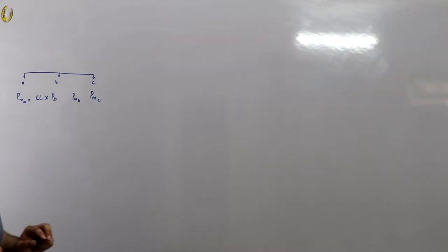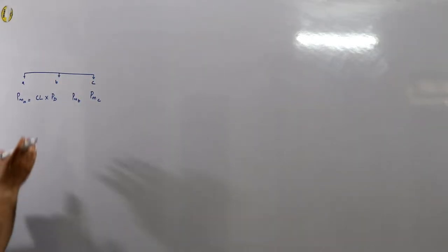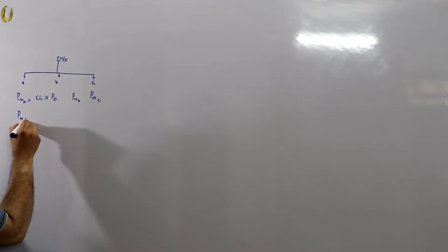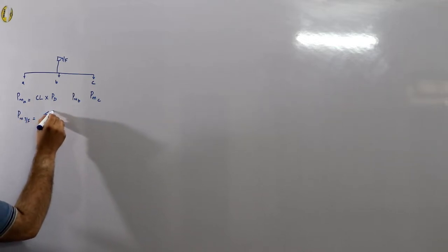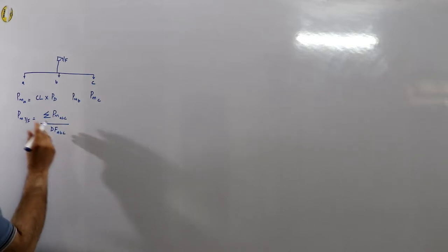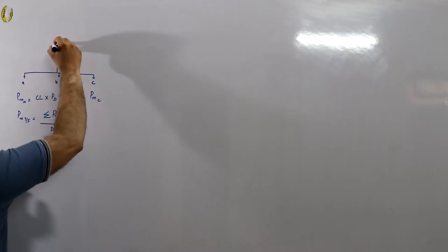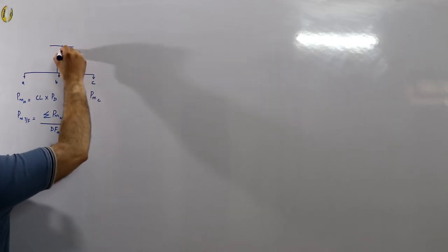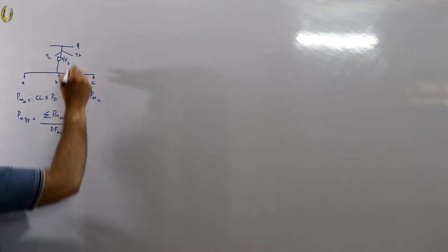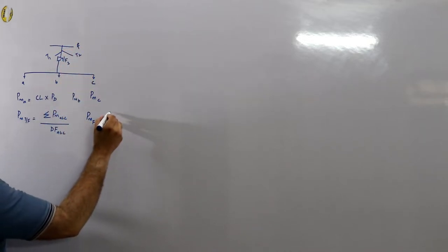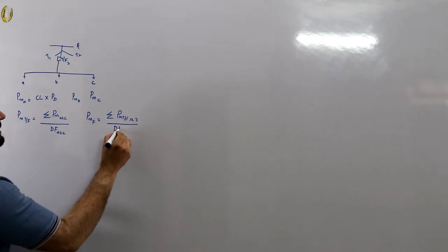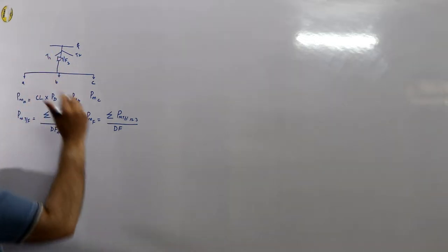These loads are connected to a transformer. The maximum demand on the transformer is the summation of the maximum demands of loads A, B, and C, divided by the diversity factor among them. This transformer is connected to a feeder, and there are multiple transformers — transformer 1, 2, 3. The maximum demand on the feeder is the summation of the maximum demands of the transformers divided by the diversity factor among the transformers.